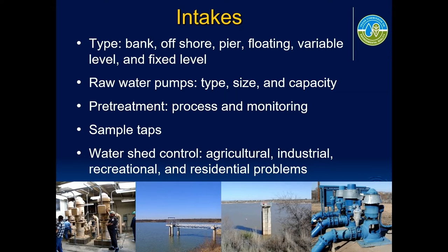It's always interesting to look at the pre-treatment that takes place in and around the intakes. In the old days, when we could use chlorine as an oxidant, we chlorinated at the intakes — both for disinfection protocols and to chemically take care of things that could be oxidized out of the water, which simplified our treatment process considerably. But when we lost the ability to use chlorine as an oxidant, we had to go to other things. The two things you see most often are chlorine dioxide as an oxidant, and permanganate — either potassium permanganate or sodium permanganate.